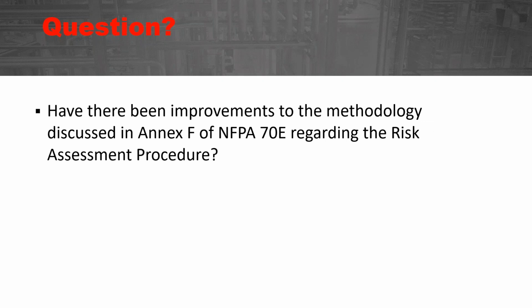Have there been improvements to the methodology discussed in Annex F of NFPA 70E regarding the risk assessment procedure? Charlie, I think you can answer this question. Informative Annex F, which is risk assessment and now risk control, was revised greatly in the 2018 edition of 70E. And I think it has been made simpler to go through and to determine the risk, to use the matrix that is up there. So it's still, of course, anything in the informative annexes is just information only. But when we're required to do a risk assessment, this is a great place to start.